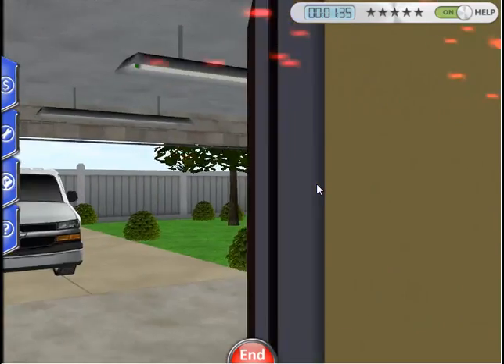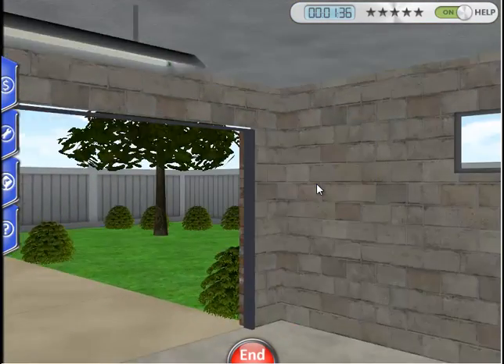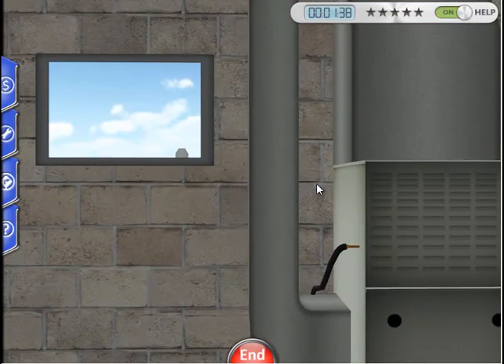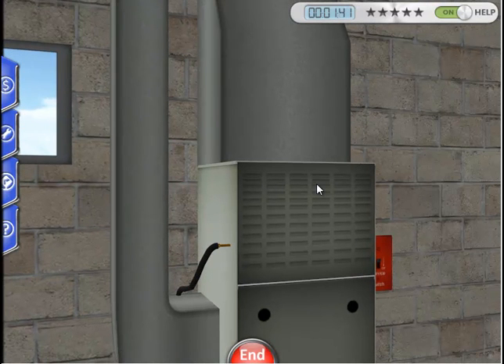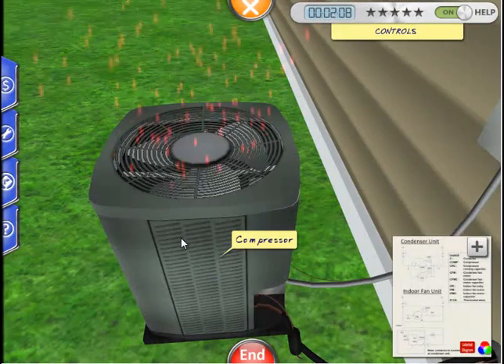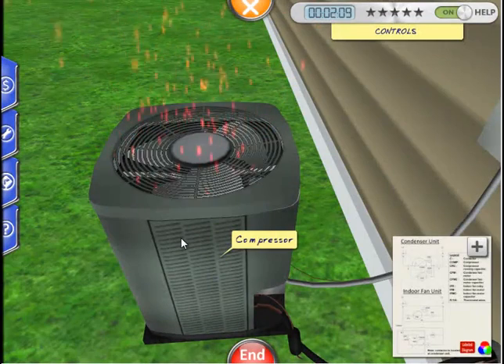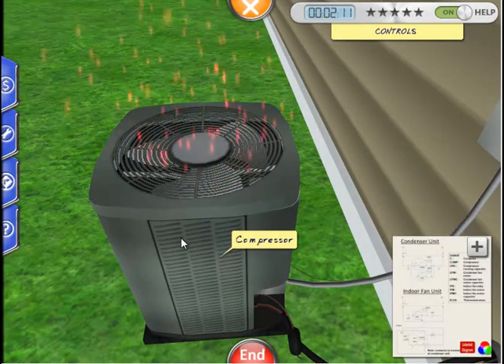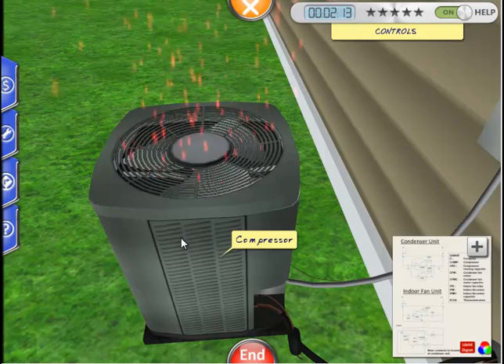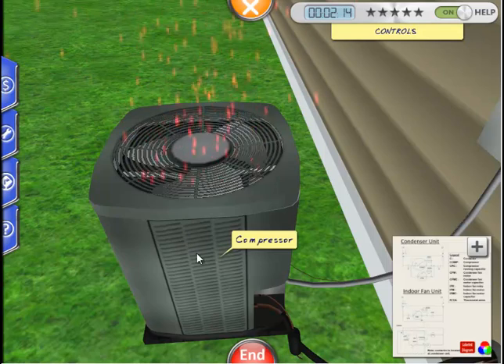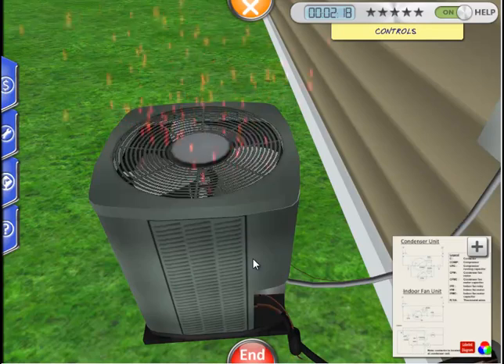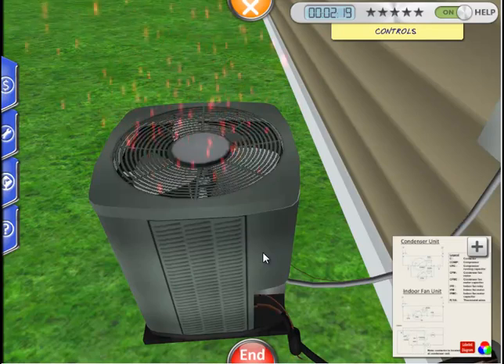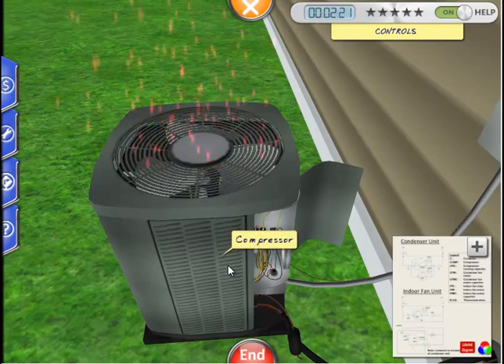We know that the indoor fan is operating because there was airflow coming out of the supplies. As we walk in the garage, we can confirm this by listening to the indoor fan motor running. Let's go outside to investigate the compressor and outdoor fan. We can immediately see that the outdoor fan is operating because it is spinning and blowing hot air out of the top of the condensing unit. We can also hear the hum of the compressor, but let's confirm that by using our ammeter.